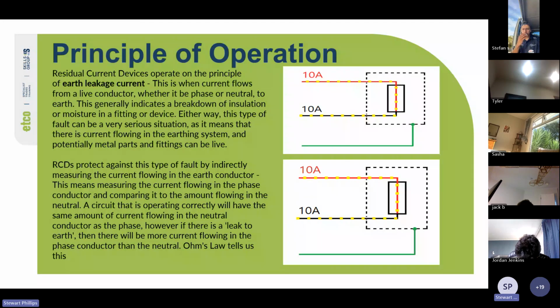Cool. So the principle of operation: the residual current device or RCCB operates on earth leakage current. This is when current flows from a live conductor to earth, phase or neutral. It generally indicates a breakdown of insulation or moisture in a fitting or device. Either way, it's a type of fault that can be very serious, as it means there's current flowing in the earthing system and potentially metal parts and fittings can be live.